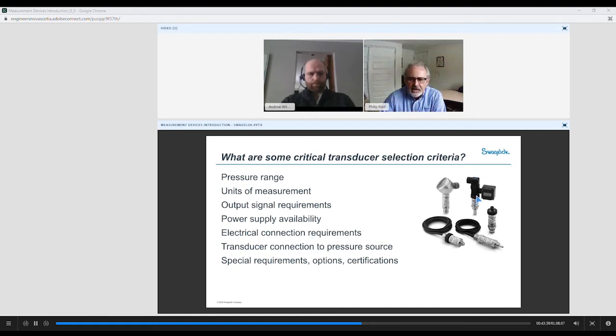What electrical connection is required? I believe there are like 17 different electrical connections available for these units, and about 9 process connections: BSP, ISO, tube adapters, fractional and metric, face seals. So there's a number available. And how it's going to be connected to the pressure source, as I just mentioned, several connections, and any special requirements. Do you need calibration certificates, material traceability certificates, certificates of conformance? Any of those are definitely available, but if you need a material traceability certificate for the materials, it has to be requested at the time of order.